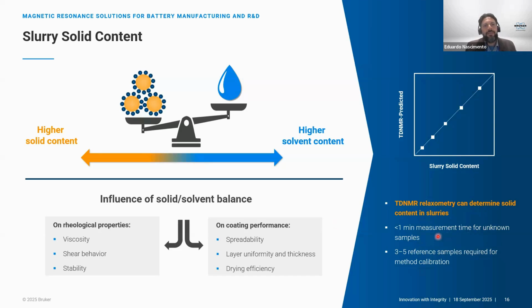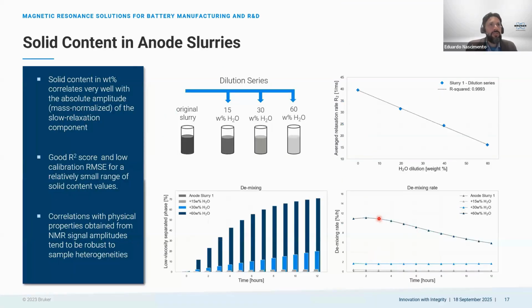So for everything that I said, for the homogeneity, for the recipe deviation, and for your slurry fraction calculation, the measurement time is something around 30 seconds, and you get all these results. So it's quite fast. Here you see an example of a slurry sample that was diluted, and you can see that this correlates very well. The R squared here is above 0.99, and you can actually see a nice example of how the mixing was happening for the samples that were diluted.